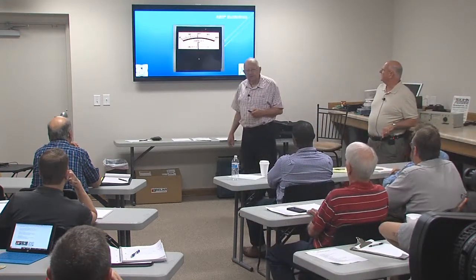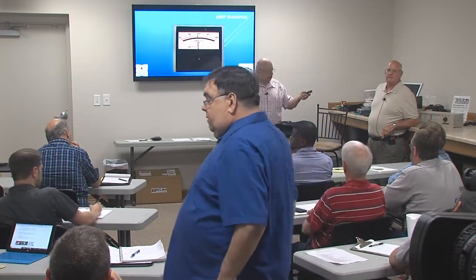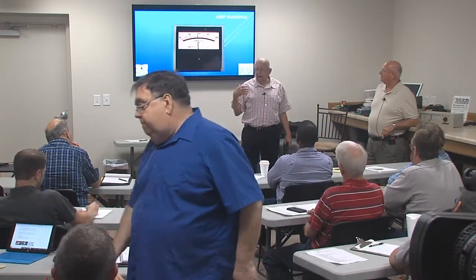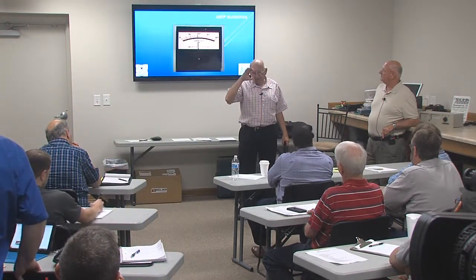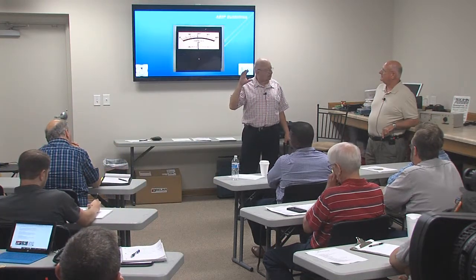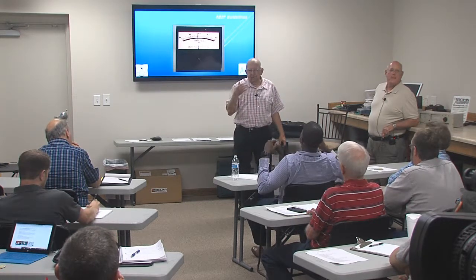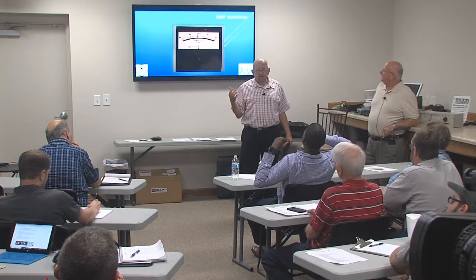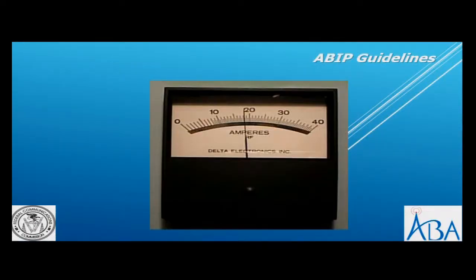If you're inspecting a directional or non-directional station, go down to the tower and have them open up the ATU box. They used to make them with little windows so you could look through, but they were always dirty and you couldn't see anything anyway, so you normally have to take the front off. Some of these boxes haven't been opened since World War I.